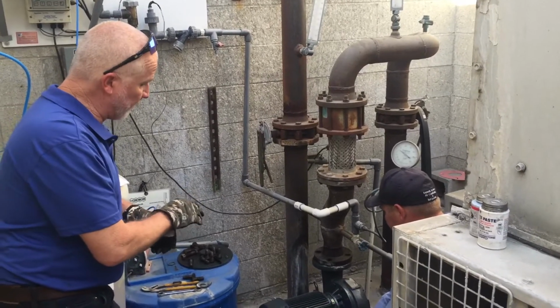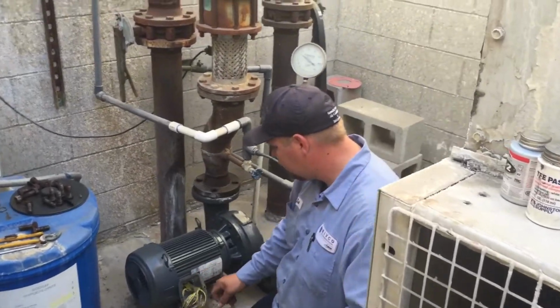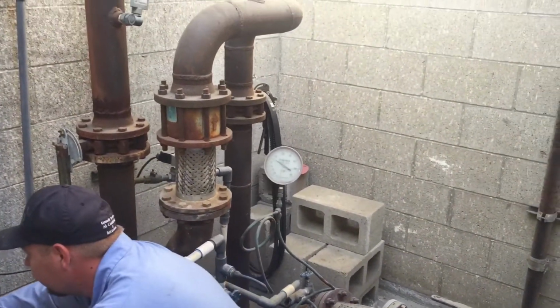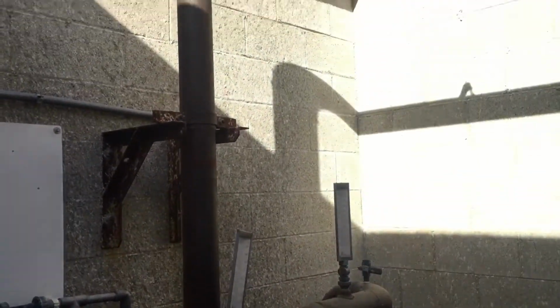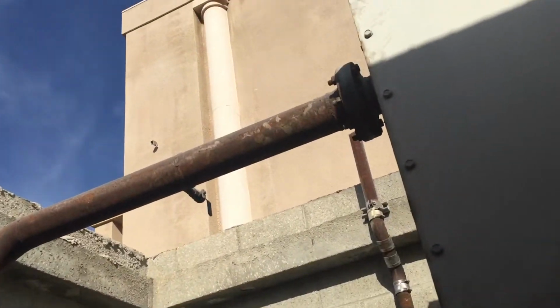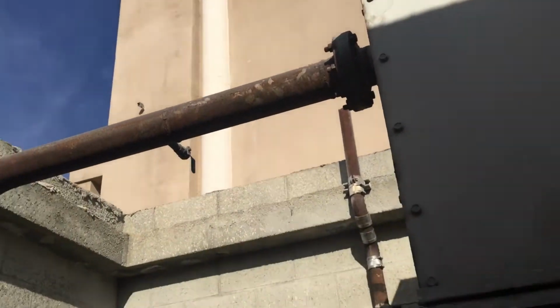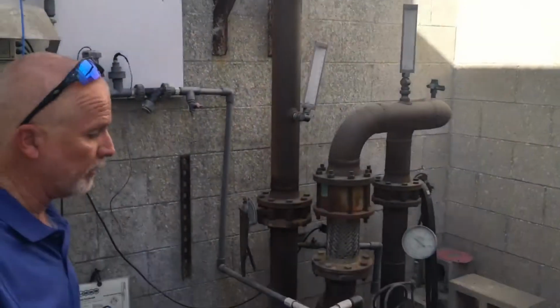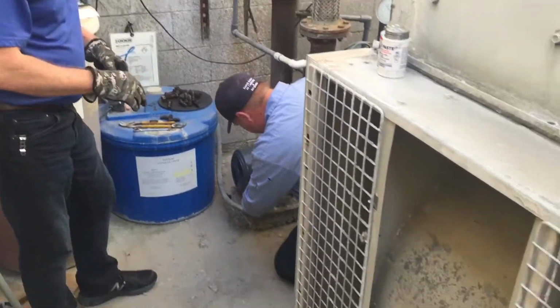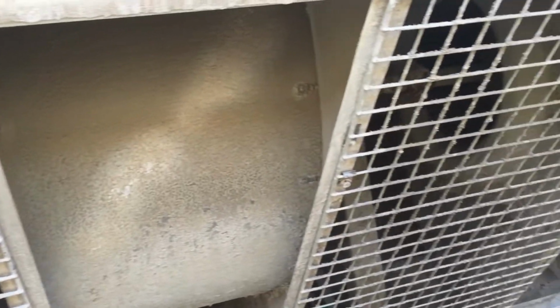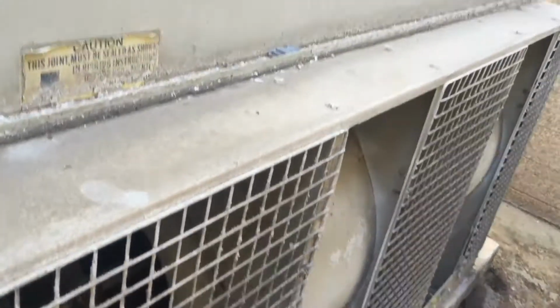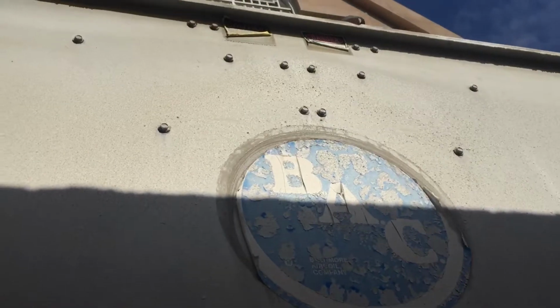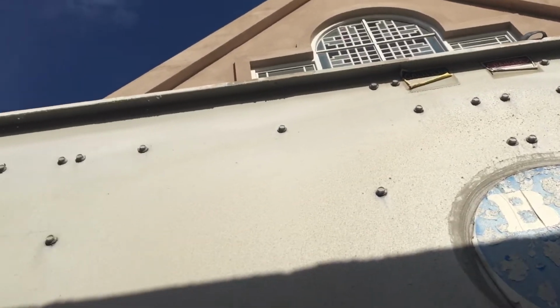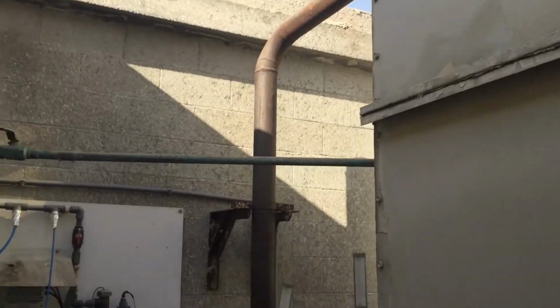Basically, this pump pumps water through what we call the condensing side of the chiller to cool the refrigerant and carry the heat we absorb out of the building in the water back out to this cooling tower, which is basically a big evaporative cooler. We reject that heat, cool the water down, and send it back inside to pick up more heat from the chiller unit. So it's a vital piece of equipment here, and it's going to be ready to rock in about 15 minutes. The chiller will be back in action to start building ice for us tonight.